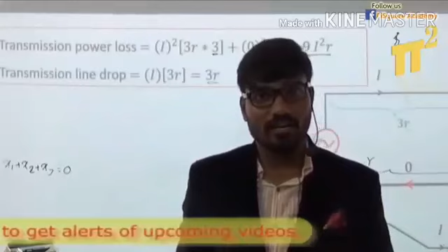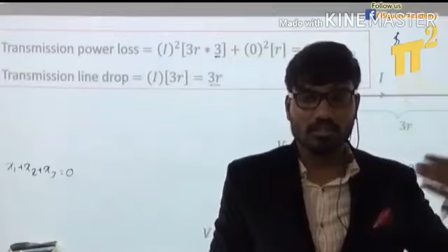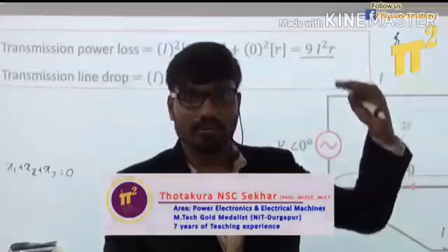This is how X1 plus X2 plus X3 equal to 0 helps us reduce the losses and voltage drop by 50%. This is the reason why we use 3 phase, not 2 phase or 6 phase or 4 phase or any other number of phases. Going for a higher number of phases would give more reduction, but at the cost of more conductors, requiring more space, greater tower height, and more complications.